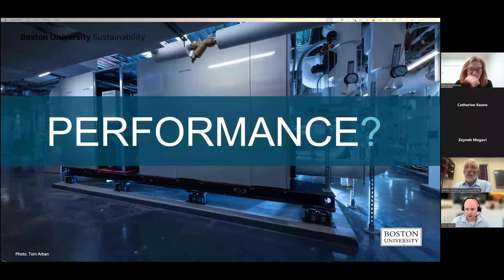Sure. So over the past year or so, we've been gathering sub-metered electrical data through the BAS to understand how the building's operating. As Dennis said earlier, we're measuring about 40 EUI. Our design target was 42, so we're exceeding that target. We're also gathering detailed geothermal system data, including hourly temperatures entering and leaving the bore field, what equipment's on, whether it's the heat recovery chillers or electric boilers, and what load they're doing, to really understand how the building is performing overall in the hybrid plant. We'll use that data to apply to new projects on campus to expand the geothermal system and potentially use this asset for other nearby buildings. Next slide, Dennis.